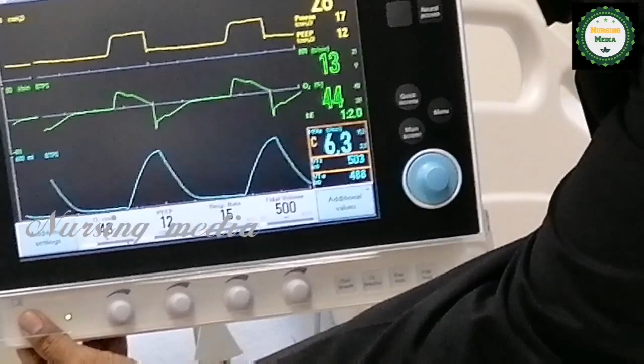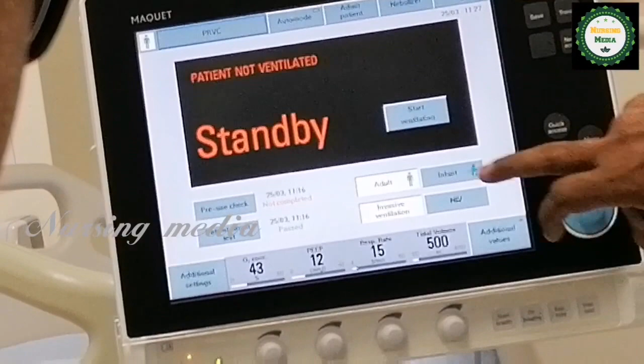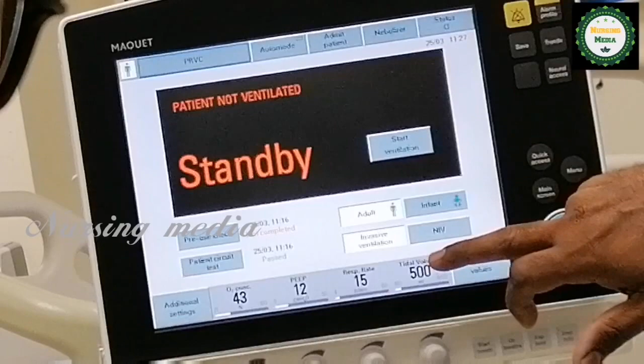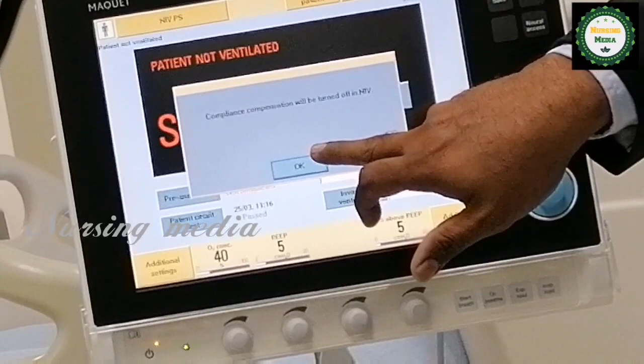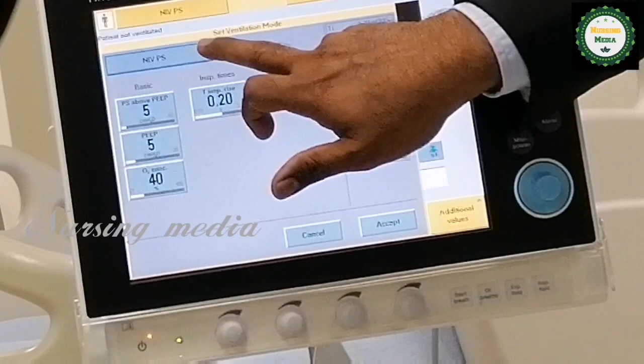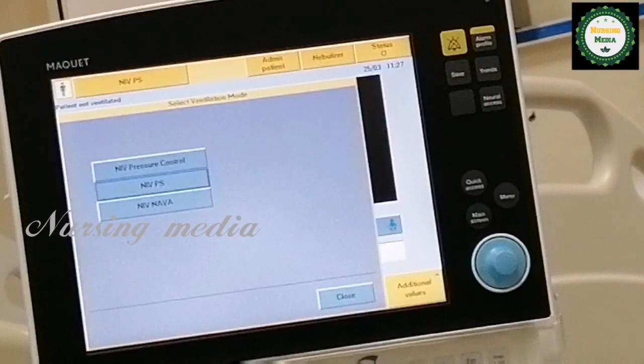Yeah, then again, how do you switch off the ventilator? It's very important. Press here and say yes. It will turn off. How do you start the ventilation? Set your category, whether adult or pediatric, whether invasive or non-invasive, then you can go to the mode. If you go non-invasive, it says compliance compensation will be turned off in NIV. Okay, no problem. So for NIV, you tap here and you will have NIV pressure support, NIV pressure control. Pressure control, as I said, you will use very rarely. Pressure support you may use very often.